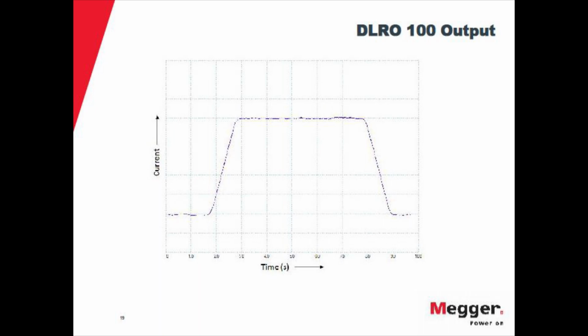If you've got dozens of tests to make and you need to get it done faster, you can try to shorten the ramp. If you don't have a ramp and you have an inductive load, you get a very large spike, which can trip the protection. If you have an inductive load, this is not the appropriate instrument to use. We have the transformer ohm meter, which is basically the same concept, but it has a higher voltage and higher energy to handle that inductance, reduce its effect, and then get the value of the resistance. I have this later on in the presentation.